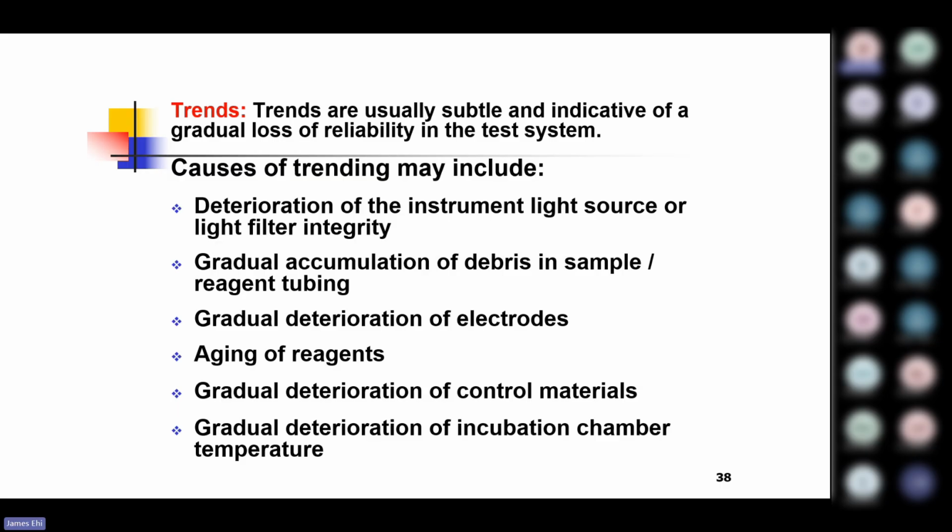If they are reagents you load on your analyzers, please take the time out to check when they expire, especially when your system does not automatically notify you that the onboard expiration has been exceeded. But if it does, then fine. Some analyzers will ask you to replace, some will ask you to recalibrate and continue. It is your QC performance post that calibration that will determine whether you should continue running that test or you should throw away the reagent.